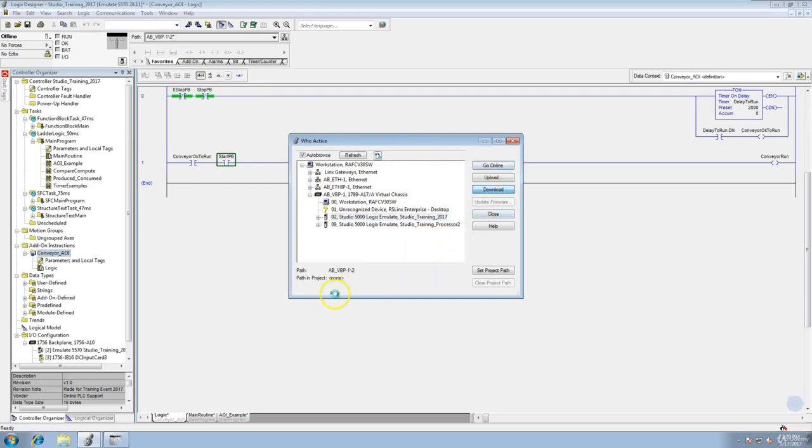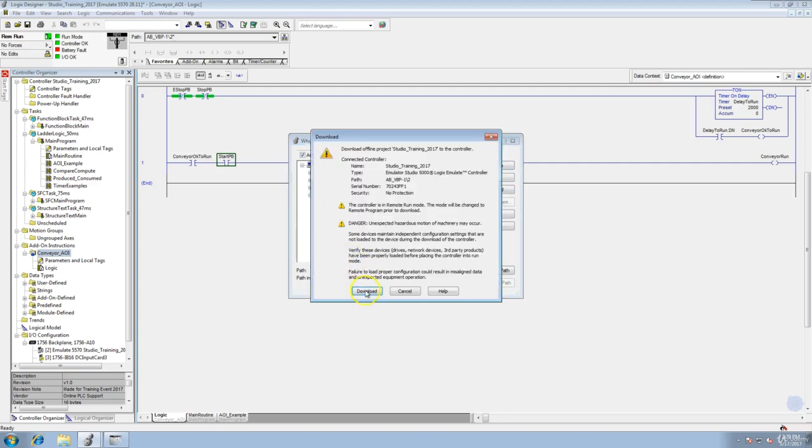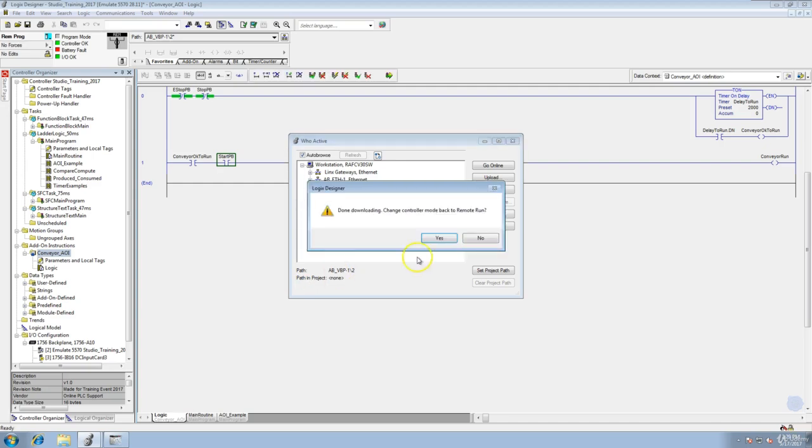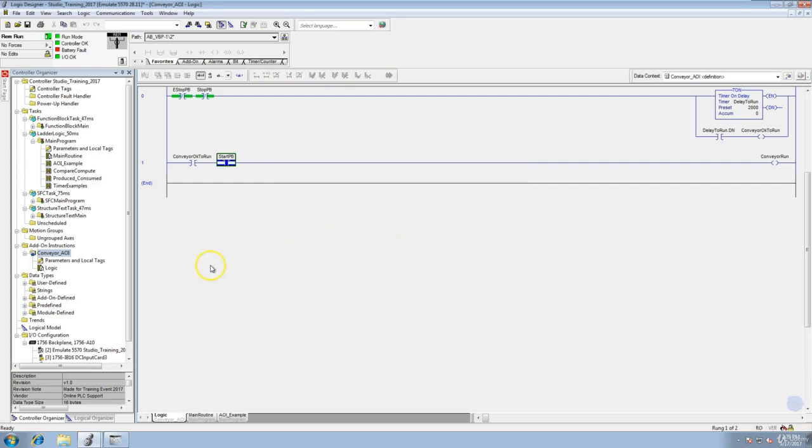And the reason we have to do that is because you cannot edit an add-on instruction online. So verify that you do have a working instruction and that it is sound before you do any kind of mass production or anything like that. Generally speaking, you want to make sure that it is a sound piece of code. But we all make mistakes, so just do your testing with it, right? Okay, so this is the base scenario right here. So I have it open. In the one instance that I have open, if you have many instances of this running, you can actually pop down this drop and select which one you want to look at.